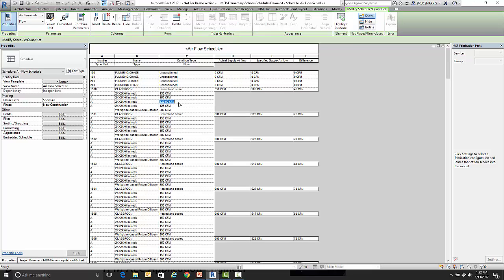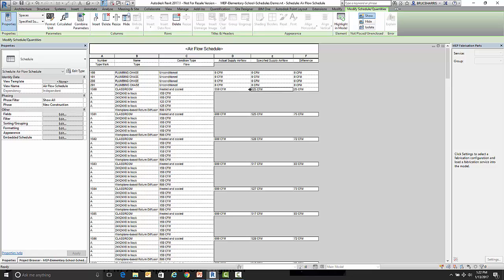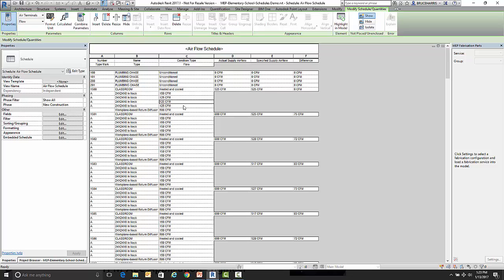So like I was saying earlier, sometimes people come in and round up specified airflow. So let's say we round ours from the calculated 505 up to say 525. So now we're within 25 CFM. So we have 25 CFM more than we actually need. So I can come in here and change one of my diffusers to be 125 instead of 150. And now I hit this exactly.